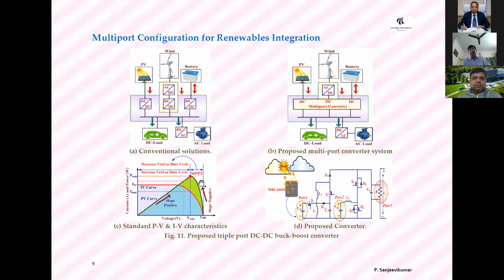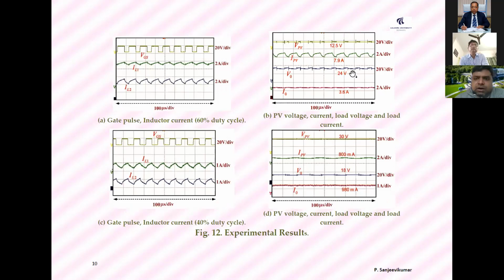In the first case, we keep the PV like a battery at 12.5 volts, with the current generated from it around 7.9 amperes. The current is very periodic with no sudden changes, which is important since it's well protected on the PV side. The output voltage is around 24 volts; we double the output from the PV, and the load current required is only 3.8 amperes. These are the PWM voltage signals for the MOSFETs and the currents on the inductor, which govern the durability and reliability of the renewable source connected to the input side of the converter. Note that all this testing is done for 60% utilization of the input power.